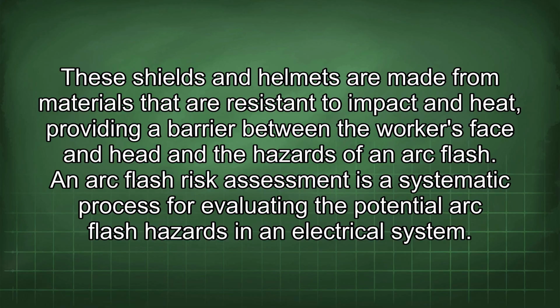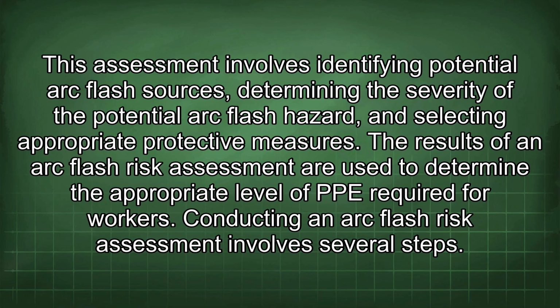An arc flash risk assessment is a systematic process for evaluating the potential arc flash hazards in an electrical system. This assessment involves identifying potential arc flash sources, determining the severity of the potential arc flash hazard, and selecting appropriate protective measures. The results of an arc flash risk assessment are used to determine the appropriate level of PPE required for workers. Conducting an arc flash risk assessment involves several steps.